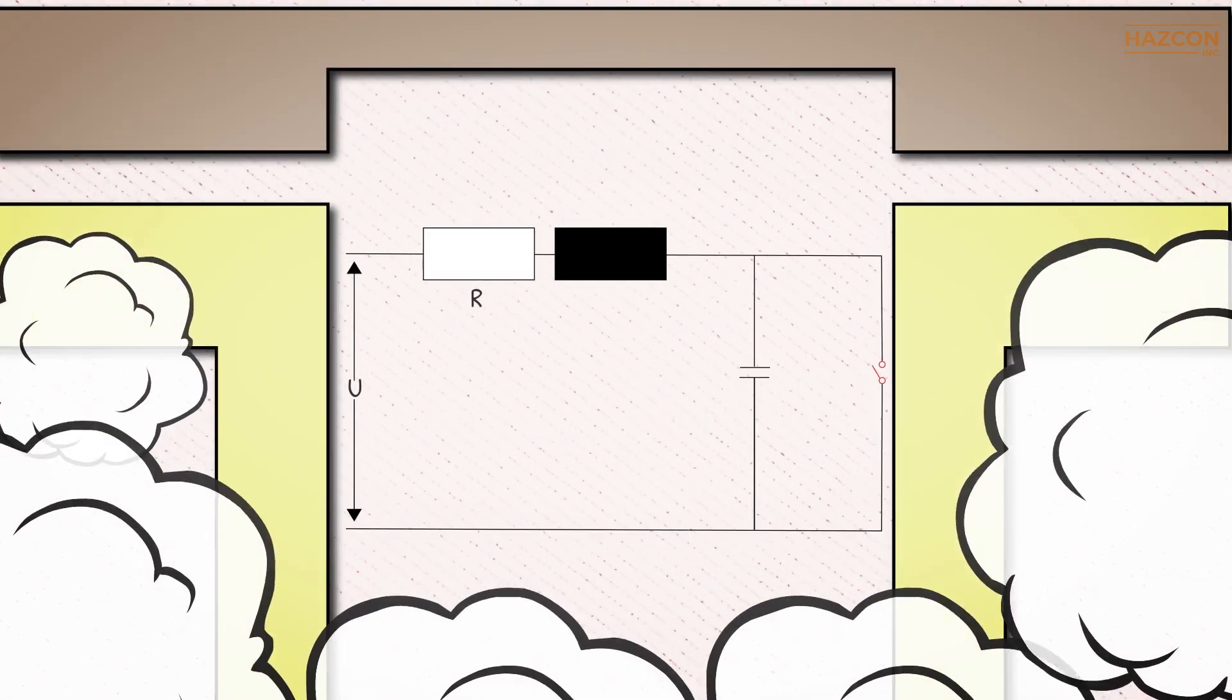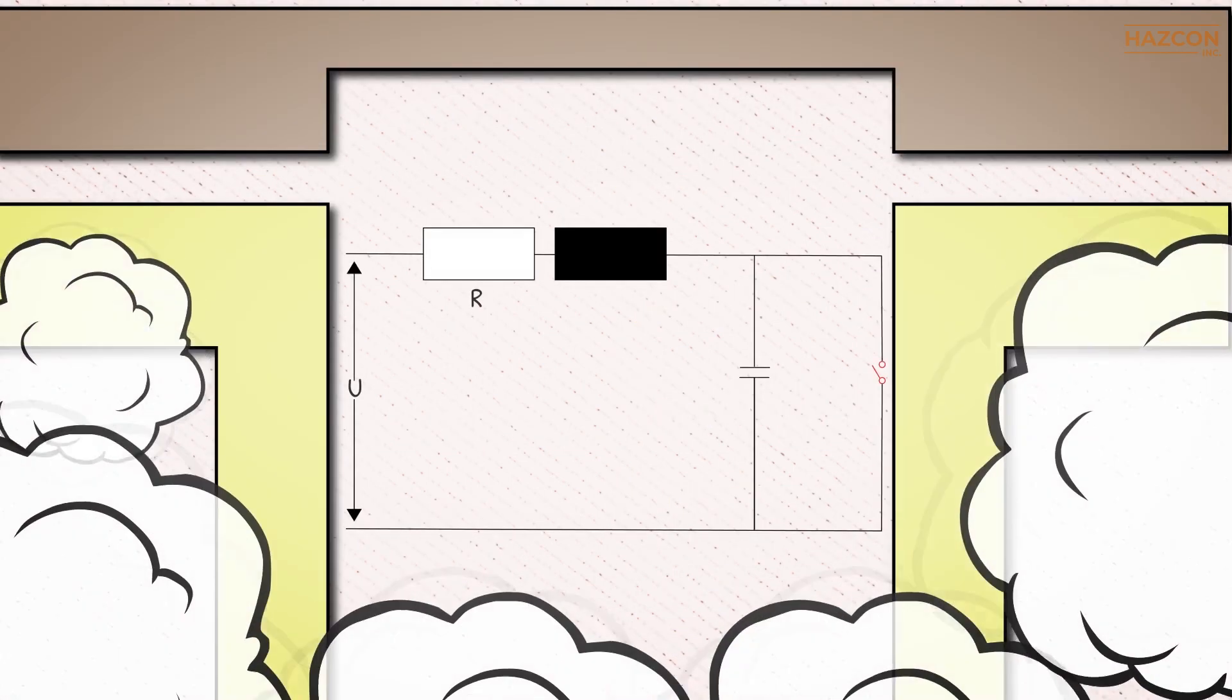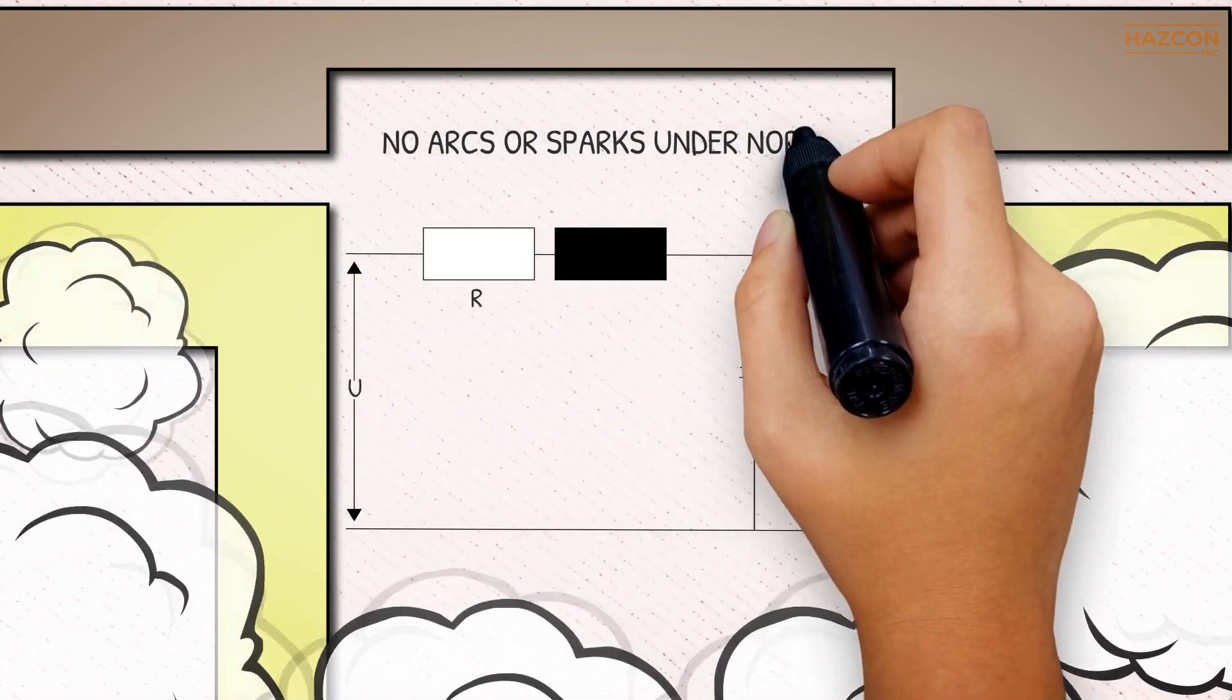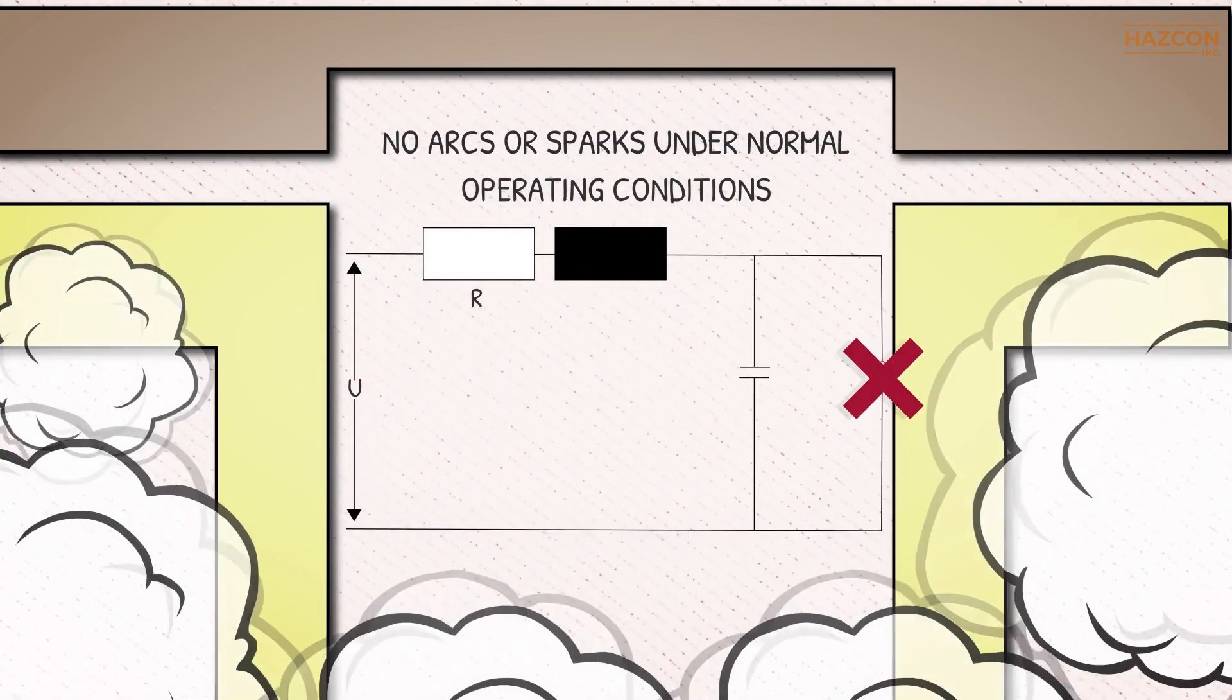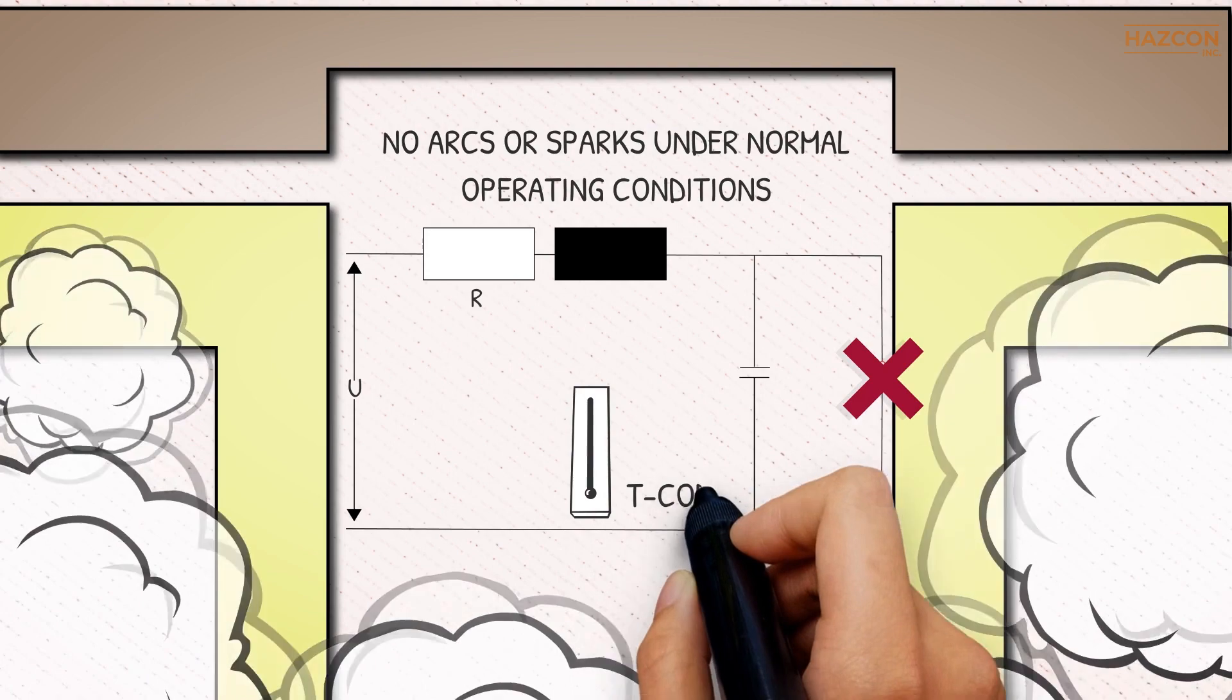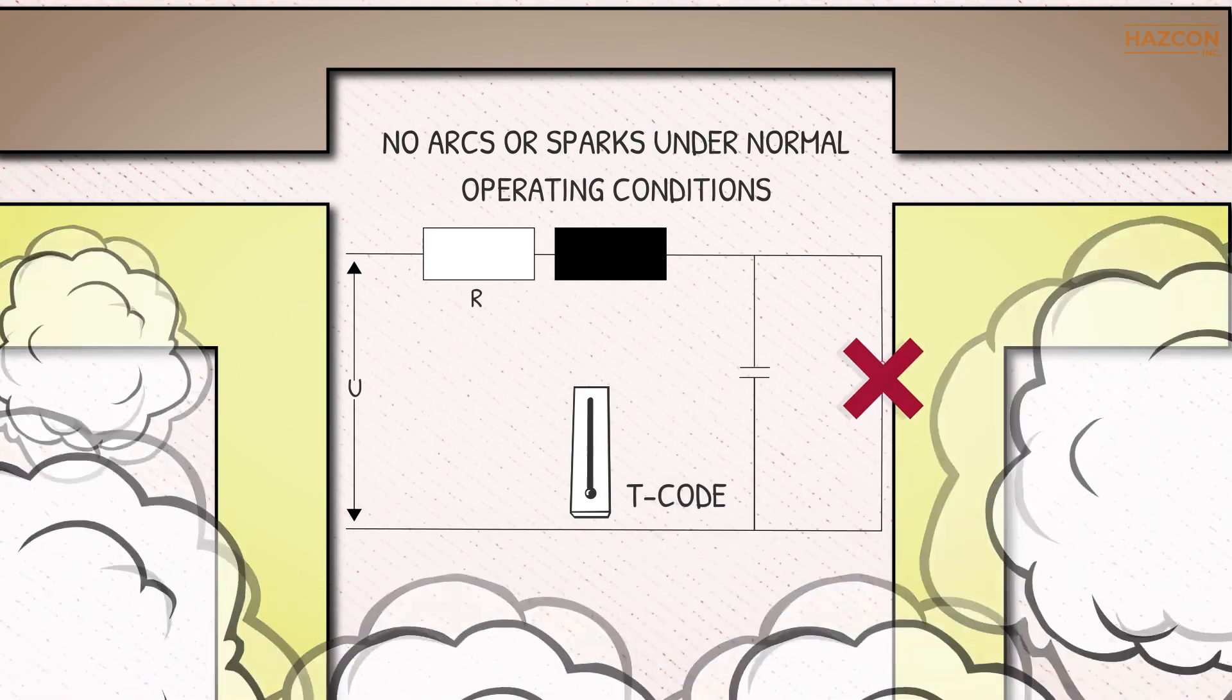Furthermore, the internal electronic circuit must be evaluated properly to ensure that there can be no arcs or sparks under normal operating conditions, and their surface temperature rise is below the T code assigned to the equipment.